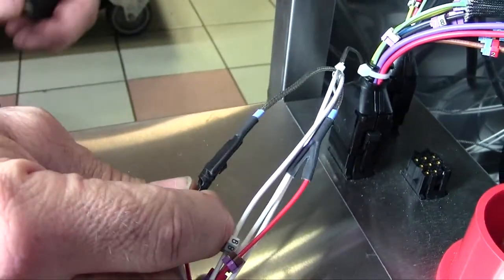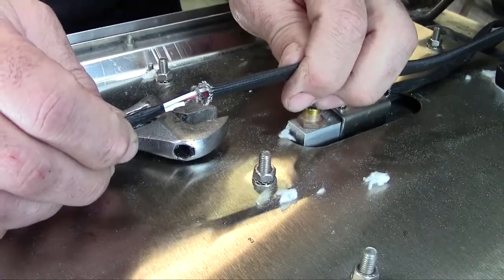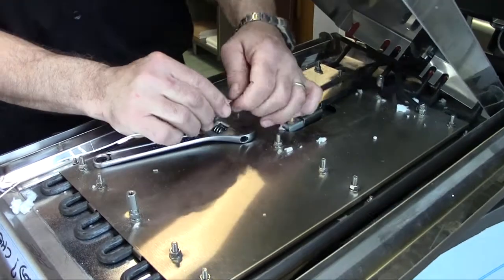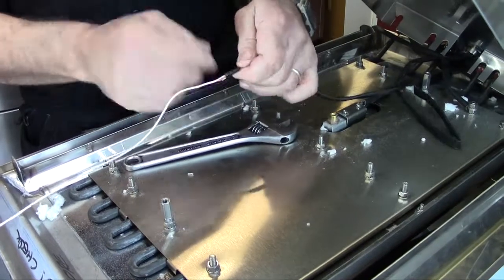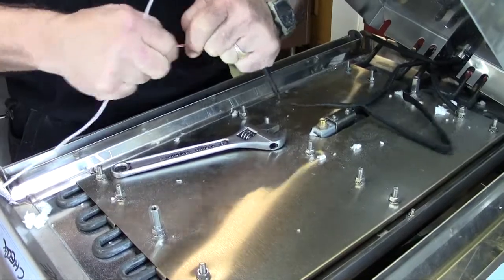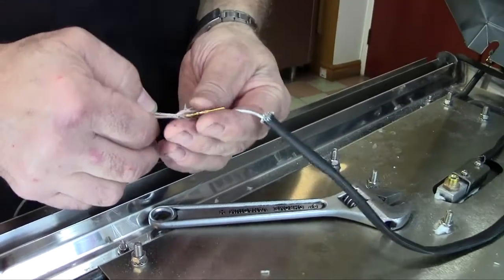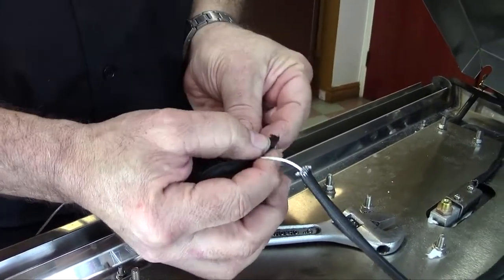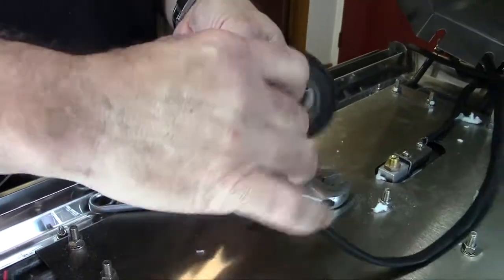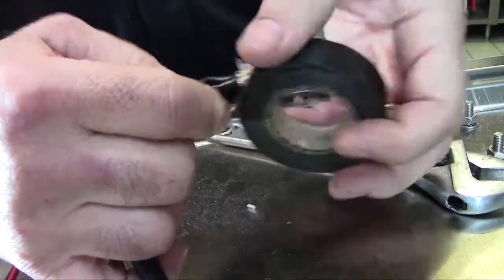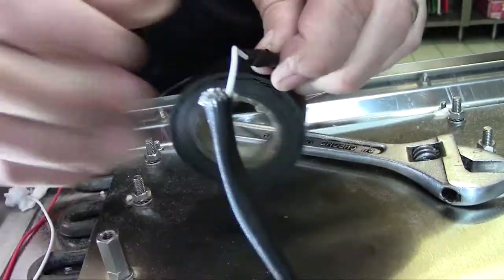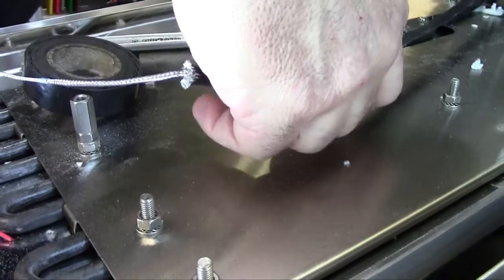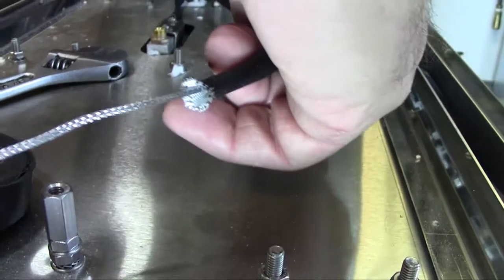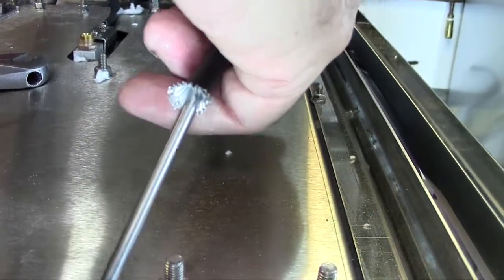And then you go back to the top. So then you pull the old probe out and you pull the wires back through to the end and disconnect that. So you get your new probe and do the reverse using your draw wire. You tape the new probe to the draw wire. Then you do the reverse and just pull it back through from the bottom, back through the conduit, through the heat bleeding, all the way till you get to the end.